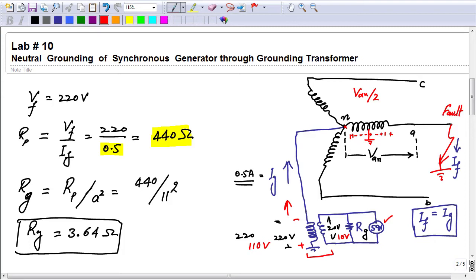Similarly, if a ground fault has occurred at 25% of the total winding from the neutral, here let's say, then the voltage between neutral and that faulty point will be VN over 4. So that would be here 55 volt. It will produce on the secondary side, according to the turn ratio, just 5 volt. Even then this fault can be detected. So this is how our voltage relay in the secondary circuit of this grounding transformer can detect a ground fault.